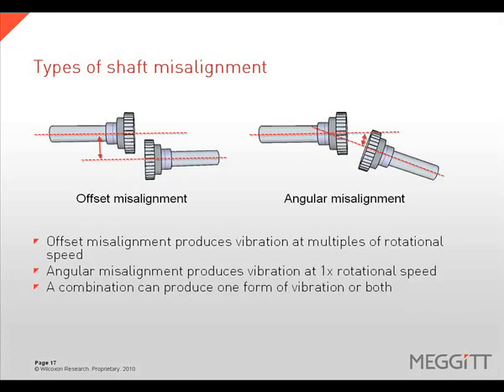There are two types of misalignment: offset or parallel misalignment and angular misalignment. Offset misalignment will commonly produce a vibration response at multiples of rotational speed — 2x, 3x, 4x, and 6x are all common.